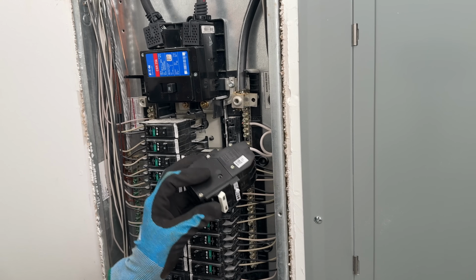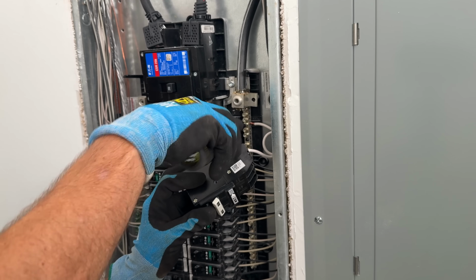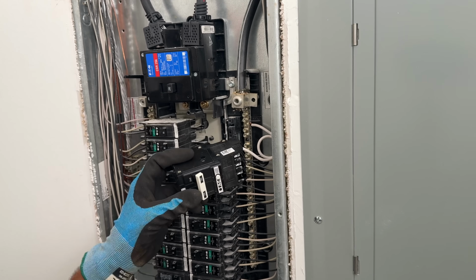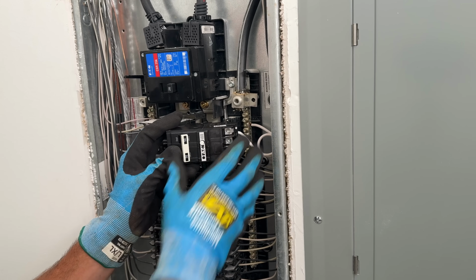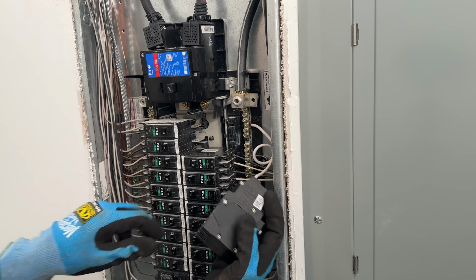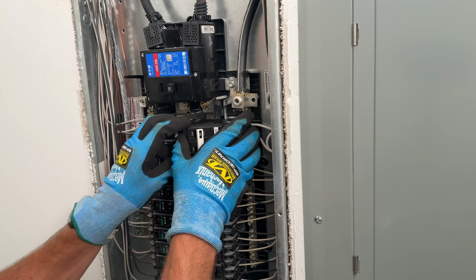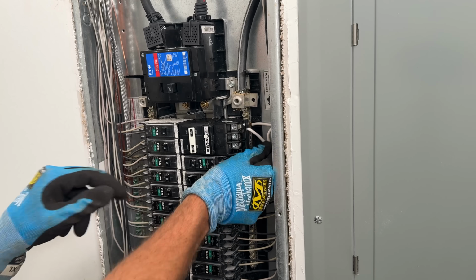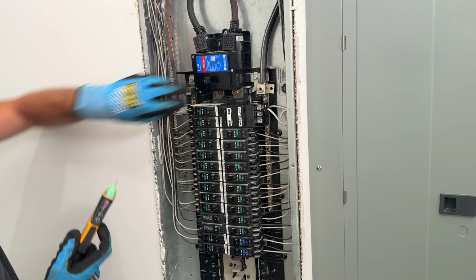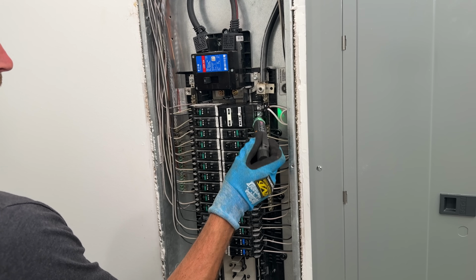Now I'm going to place this 240 volt 50 amp GFCI breaker, and this one actually has a neutral pigtail that I need to secure into the neutral bus bar. Now that bus bar internally is leveraged by these 120 breakers, and that's why they don't need the white pigtail for AFCI and GFCI protection.